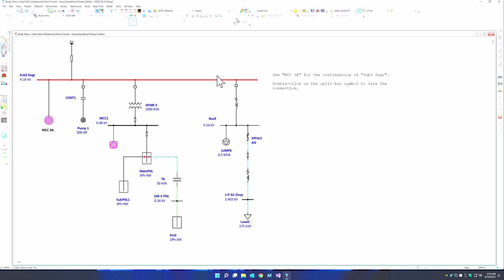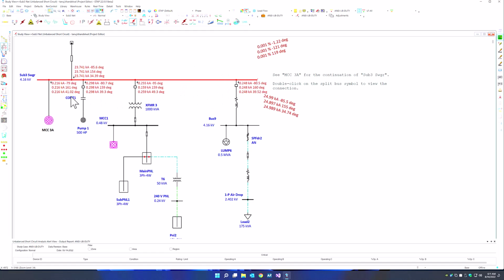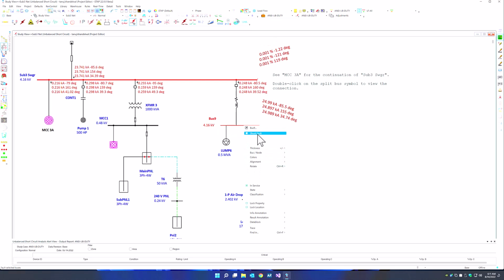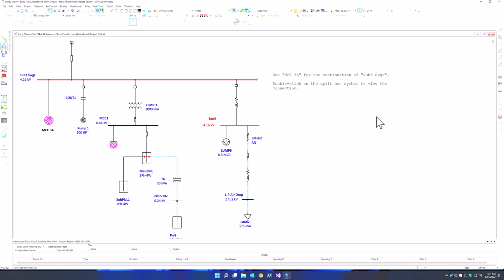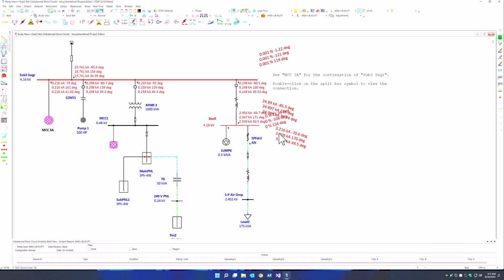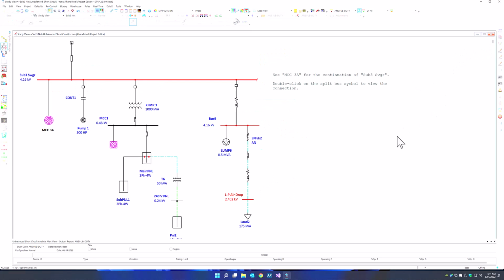In this case, I'm running a simple device duty simulation, and we can see for a combination of a three-phase as well as single-phase system, the individual A, B, and C phase currents and angles, as well as the contribution from the downstream components. You can simply right-click and place a fault and rerun the simulation, making it very easy to use, similar to the balanced short circuit module. You can pick any bus, whether it's three-phase or single phase, and perform this kind of calculation.